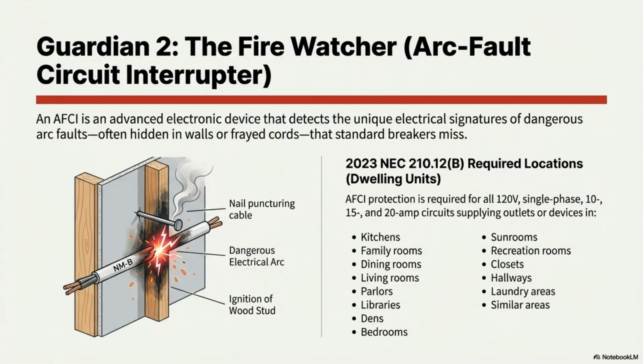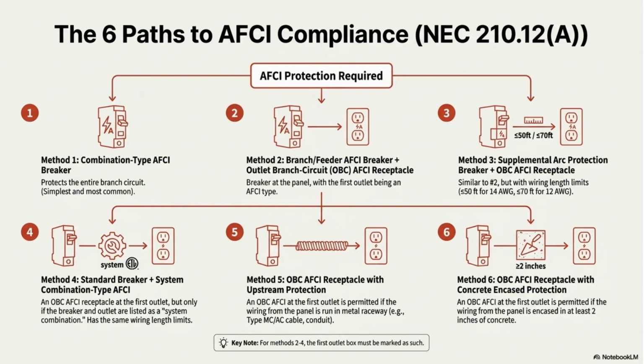Guardian 2, the fire watcher, is the arc fault circuit interrupter, or AFCI. It detects unique electrical signatures of dangerous arc faults, often missed by standard breakers. NEC 210.12(B) requires AFCI protection in nearly all dwelling unit areas. There are 6 paths to AFCI compliance under NEC 210.12(A). The simplest and most common method is the combination-type AFCI breaker. Other methods involve using branch/feeder AFCIs or supplemental arc protection with receptacles, often with wiring length limits.